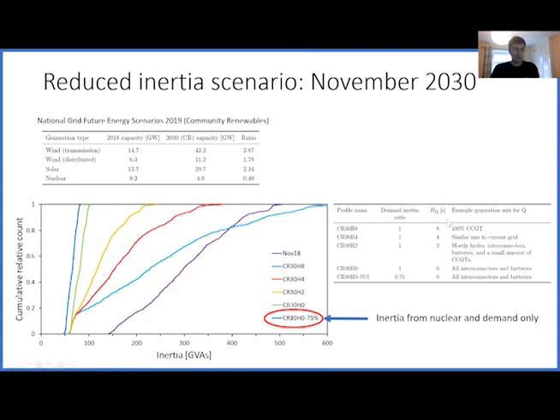Just to give the example I'm going to take forward: the worst case scenario is that inertia is only provided by nuclear and demand. In fact, demand inertia I've said is 75% of what it is now, assuming there are fewer synchronously connected demand units in 2030. The example generation mix for whatever's left over if wind, solar and nuclear don't meet the demand is, for example, interconnectors and batteries, which don't offer traditional inertia to the grid.